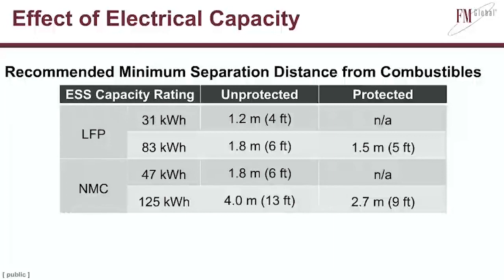Now the middle column is going to show you the separation distance. Again, this was just for combustibles. This is that 12.5 kilowatts per meter squared number. This middle column shows you how far away things would have to be when you don't have any sprinkler protection. And when we go to the far right column, it'll show you how far things can be when you have sprinkler protection. Now, I wasn't able to run every test sprinklered, just a large test, and that's why you see that NA for not applicable.